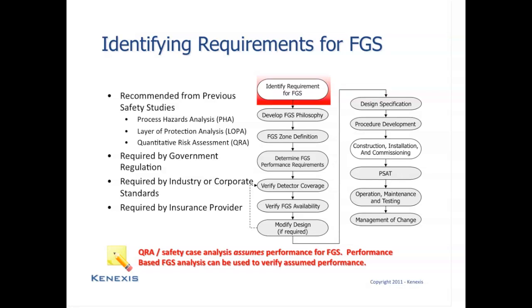Also, there are industry standards and corporate standards that stipulate that if you are going to operate a certain type of facility or certain types of process equipment, that equipment or those facilities need to have fire and gas detection and suppression systems incorporated as part of their design. And finally, in some cases, insurance providers, as they audit your facility, will be checking to see what degree of fire and gas systems are installed, and if the insurance assessor determines that your fire and gas system is inadequate or nonexistent, they may recommend that you implement such a system, with a penalty for not implementing ranging from increased premiums to outright refusal to underwrite your insurance policy altogether.